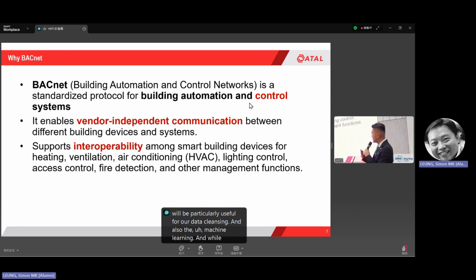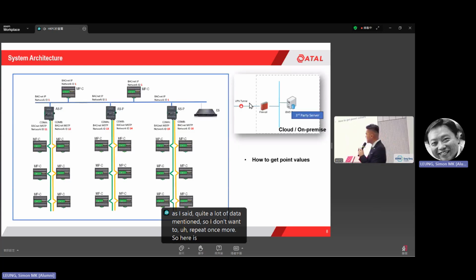And why BACnet? As I said, quite a lot of speakers mentioned the reasons, so I don't want to repeat once more. So here is the typical BMS network. If our controller and device are BACnet ready, that means they have the BTL certification, we can simply connect another server to this BMS network to obtain the data. We can create the BACnet point for the third-party server. So it is quite easy to obtain the data if these devices and controllers are BACnet ready.